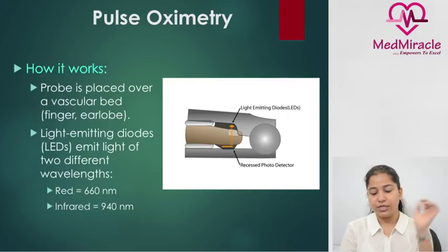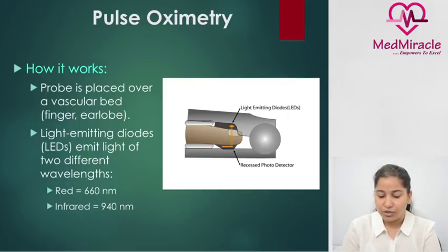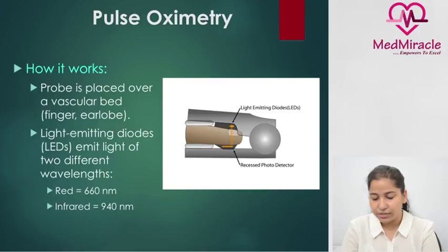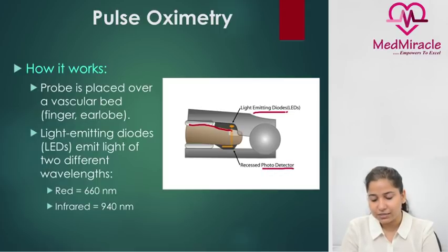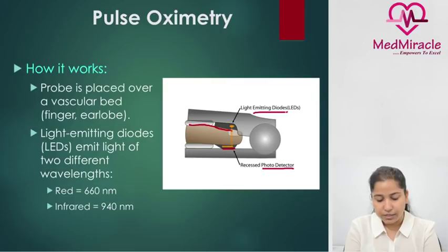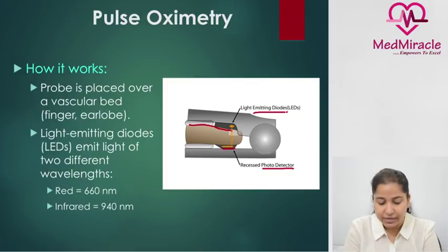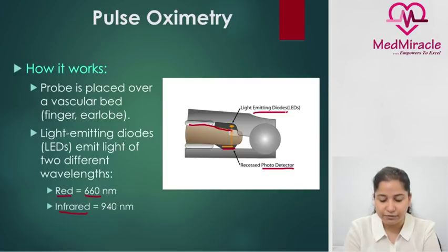How does pulse oximetry work? The finger fits inside the monitor, which has a light emitting diode and a photo detector present in the lower surface. The light emitted belongs to two different wavelengths: red at 660 nanometers and infrared at 940 nanometers.